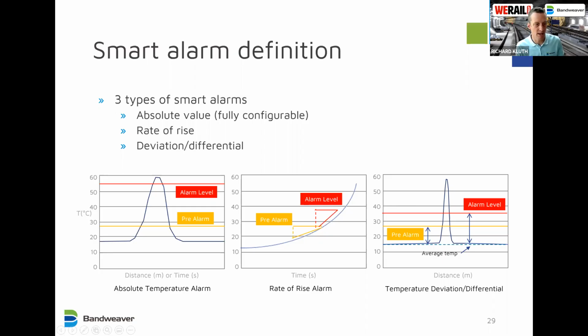And similarly, the temperature deviation alarm triggers when there's a temperature peak within a zone that differs from the average value. And again, 9 or 10 degrees C is a typical value for a tunnel. And this would trigger much earlier than the absolute temperature alarm. But in some cases where you have a slow burning fire, the rate of rise may not trigger, and so the temperature deviation or differential alarm is a good tool to have in the armory.